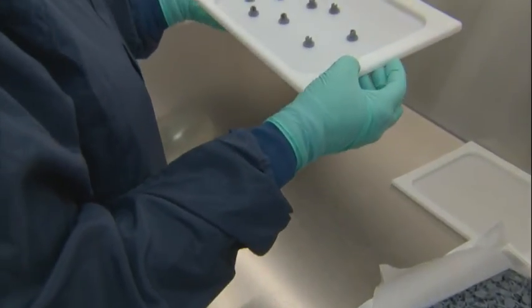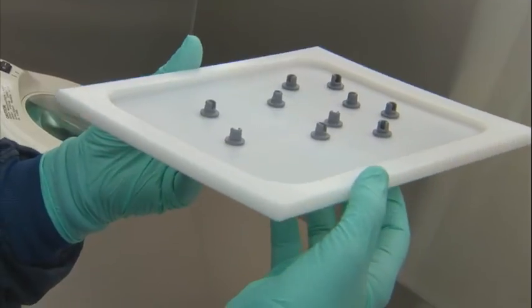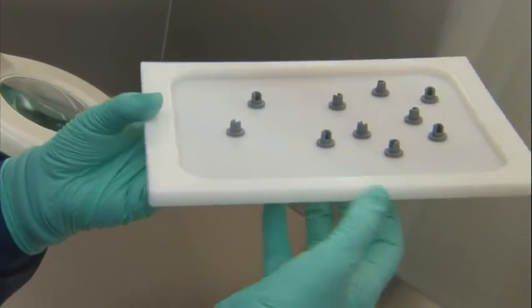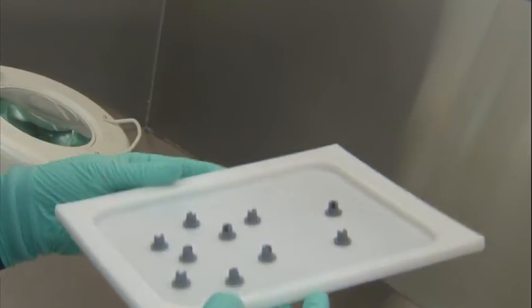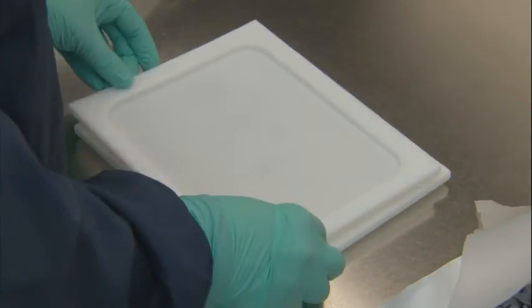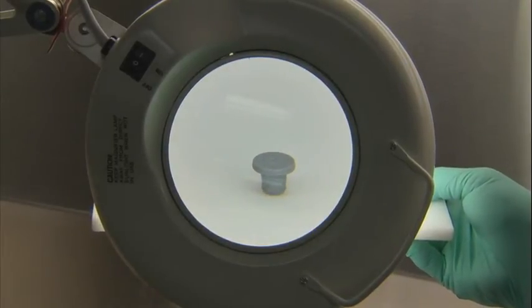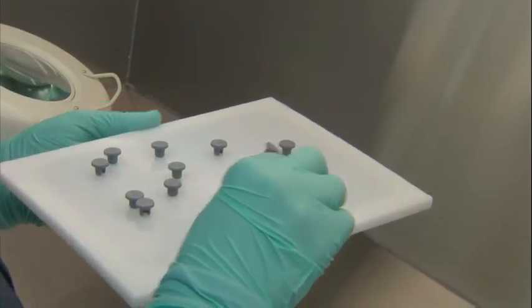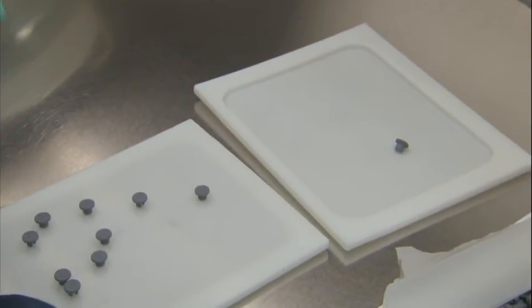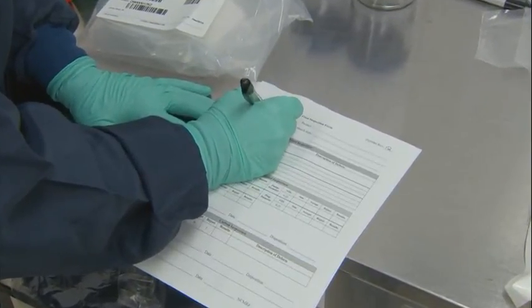The inspection criteria for WEST is as follows: a qualified inspector with visual acuity should use proper lighting. Observations are made from approximately 18 inches with the naked eye. Place a number of items on a cleaned, shallow tray with stoppers or plungers oriented in the same direction. Rotate the tray 360 degrees, looking at all sides of the component. In the event of a question, the inspector may use magnification to help discern the issue, though magnification is not used by WEST for the initial examination. Set any part aside on a second clean tray for documentation of the observed attribute. We recommend all paperwork be kept in the designated area outside of the laminar hood. Flip the stoppers or plungers over and repeat the inspection on the other side.